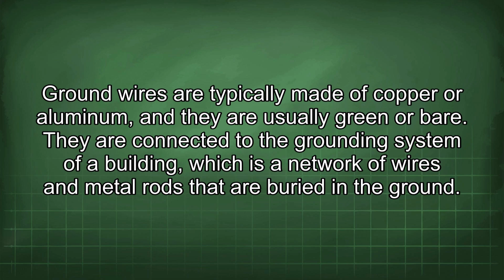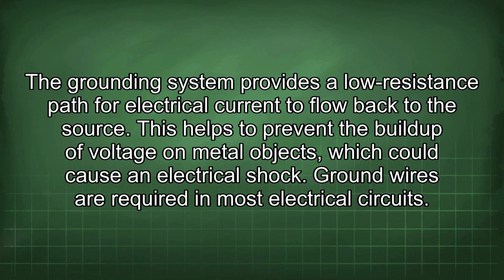They are connected to the grounding system of a building, which is a network of wires and metal rods that are buried in the ground. The grounding system provides a low-resistance path for electrical current to flow back to the source. This helps to prevent the buildup of voltage on metal objects, which could cause an electrical shock.